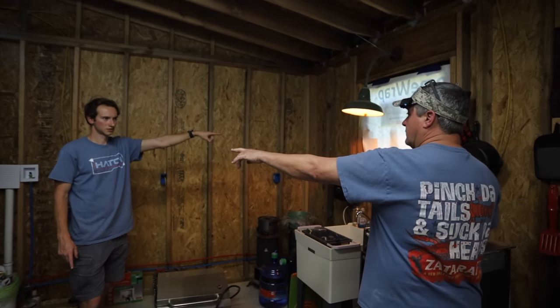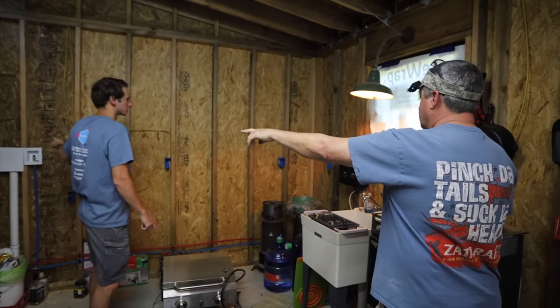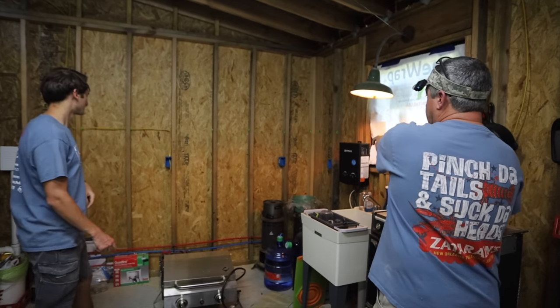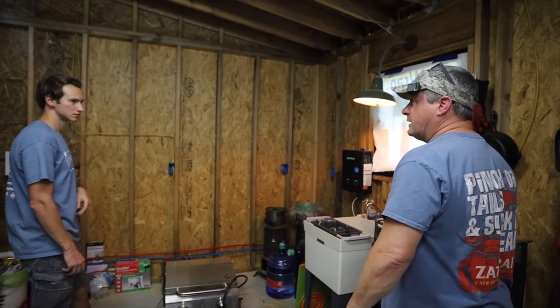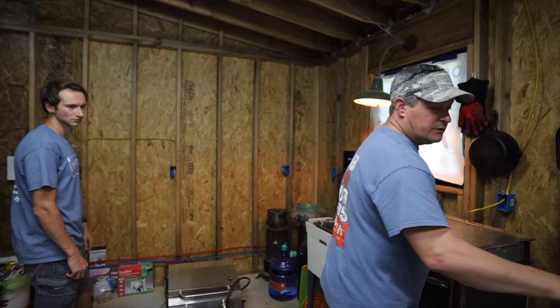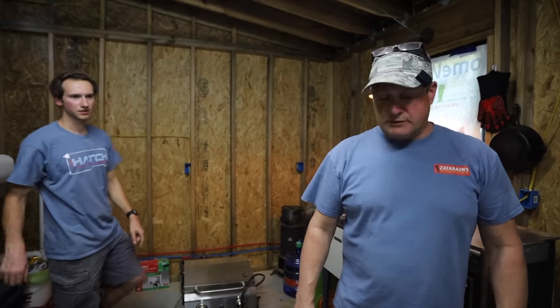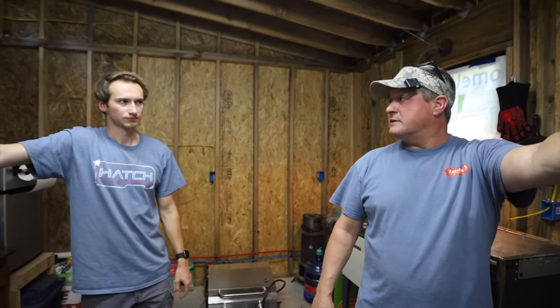You're going to get your 220 for the dryer, 110 for the washing machine, another circuit for your disposal. This is your second small appliance circuit — 20 amp for the kitchen. We're going to feed an additional outlet, and then once the countertop comes out, you'll have one for the outlet at the end. Then you'll pick one more for the lighting and for the outlets over here, so you can hit your outlets, hit switch, and carry on. Also pick up one in the den.